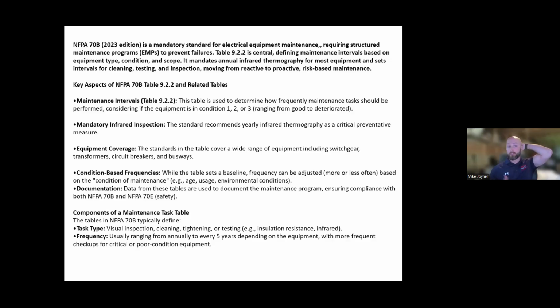One of the top lines on the next page is infrared scanning. The way we used to practice it, we'd do one year of infrared scanning, which involves visual inspection and looking for code violations. The next year we'd do de-energized maintenance, and the following year another infrared scan. We'd scan the building, find problems, fix them during the de-energized maintenance, then the following year ensure the problems were resolved. Because of this new code and this table, everything has to be infrared scanned once a year, every 12 months, broken down by condition, telling us the frequency for other practices.